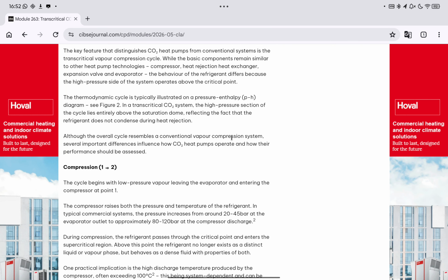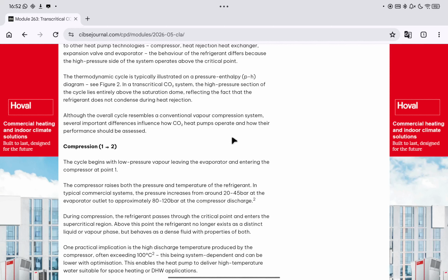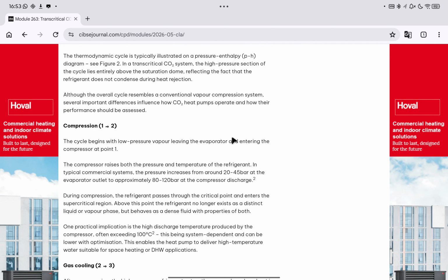Compression. The cycle begins with low pressure vapor leaving the evaporator and entering the compressor at point 1. The compressor raises both the pressure and the temperature of the refrigerant. In typical commercial systems, the pressure increases from around 20 to 45 bar at the evaporator outlet to approximately 80 to 120 bar at the compressor discharge. During compression, the refrigerant passes through the critical point and enters the supercritical region. Above this point, the refrigerant no longer exists as a distinct liquid or vapor phase, but behaves as a dense fluid with properties of both.